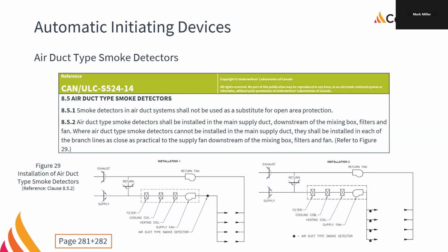We only care about the supply air. The goal is to not put smoke into the floor areas. That's what we're trying to stop. So we put our smoke detector, our duct smoke, downstream of all filters, cooling coils, heating coils, supply fans. We put them downstream.